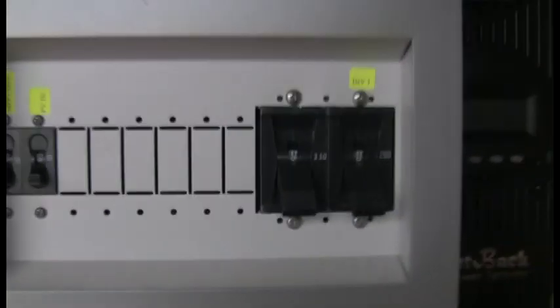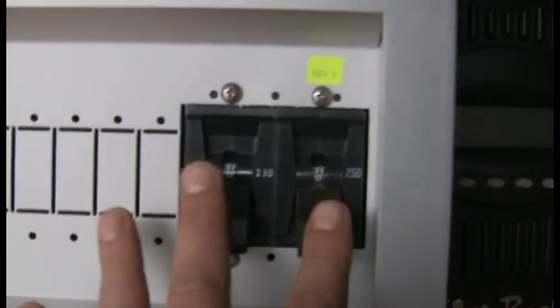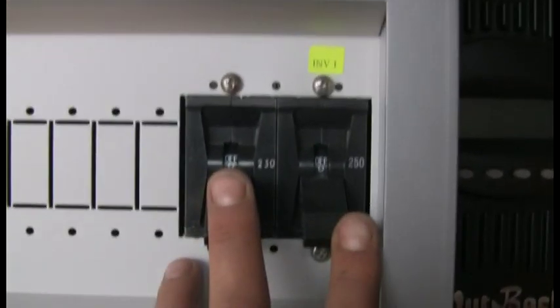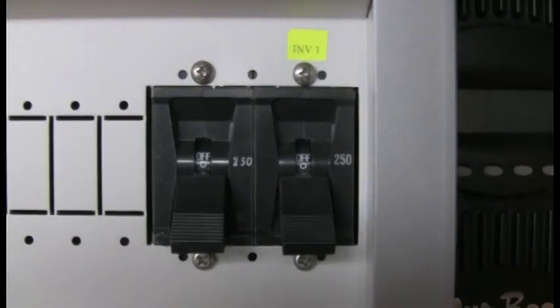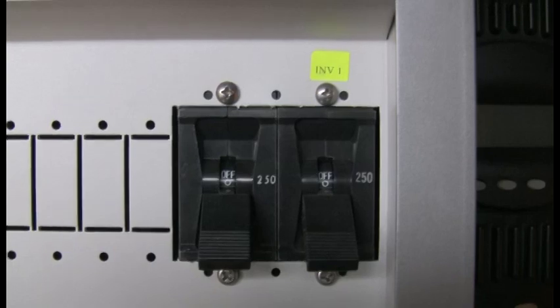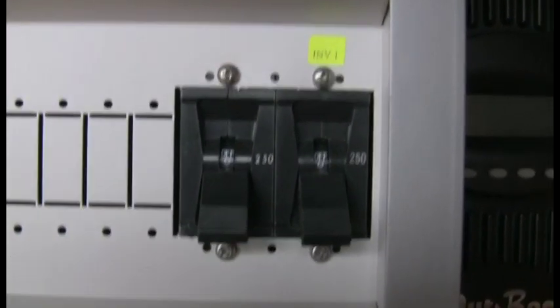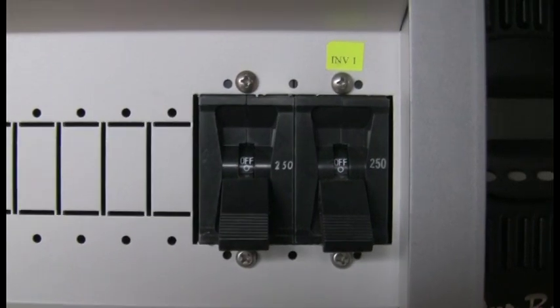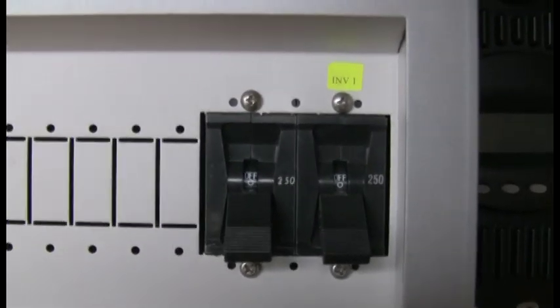Now, as you can see, the mate is off and the charge controller is off. The way this powers up is on the DC side first. And these two breakers control the battery supply to each inverter. And of course, you'll note that these are 250 amp DC rated breakers, which is more than enough to handle the current that each inverter can handle. You'll see that all of the indicator lights are off. So this is completely powered down right now.